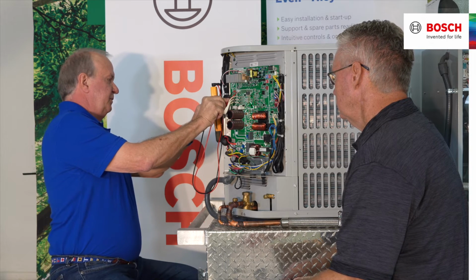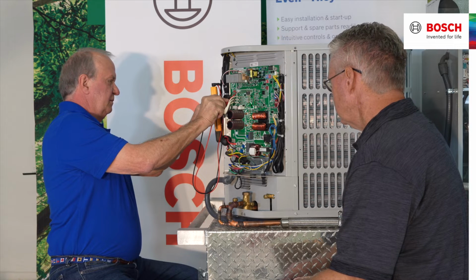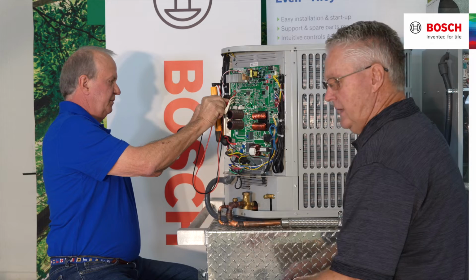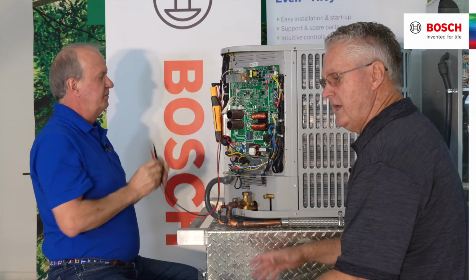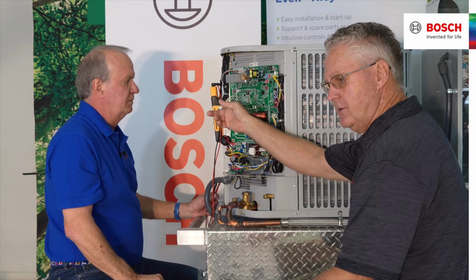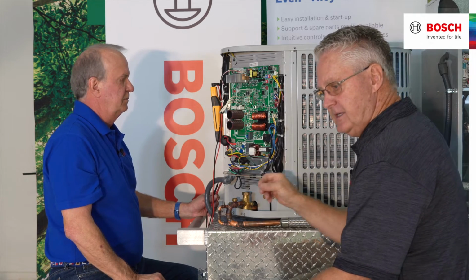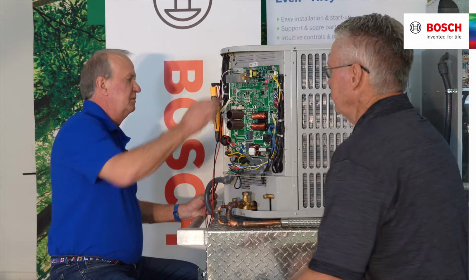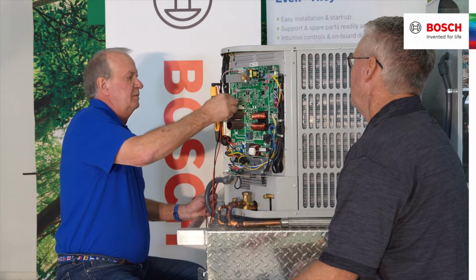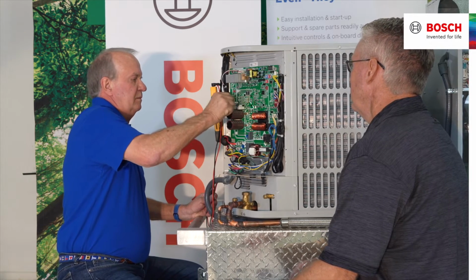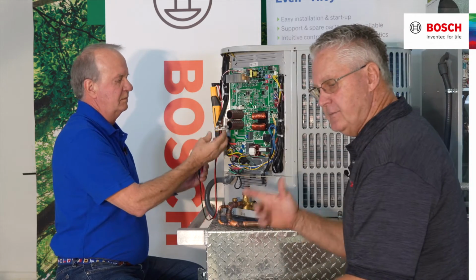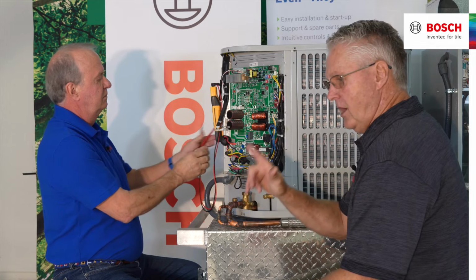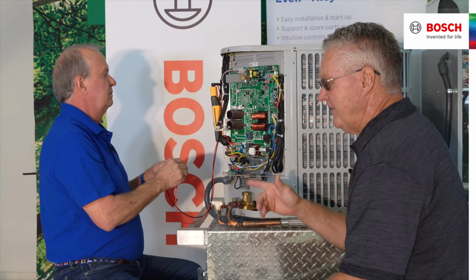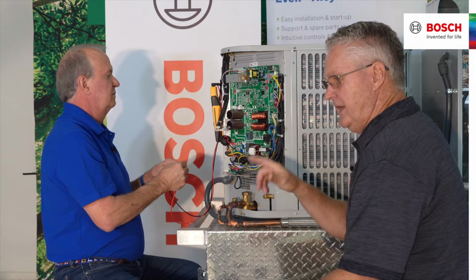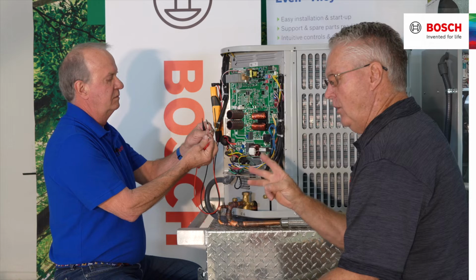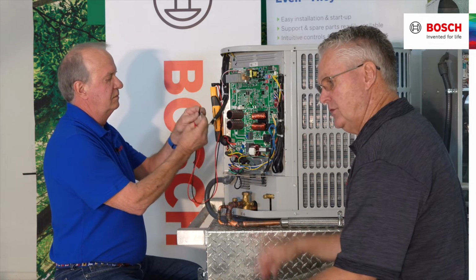It's coming down. 32.4. So right now we're less than 42 DC volts, so we can unplug the U, V, and W wires, and we're going to ohm out this GMCC compressor on this Bosch IDS unit. Now this compressor is a GMCC compressor. We are not looking for a common, start, and run, but we're looking for 1.5 ohms or less on each one of the terminals, U, V, and W, and all three of those numbers are going to be the same if it's a good compressor.